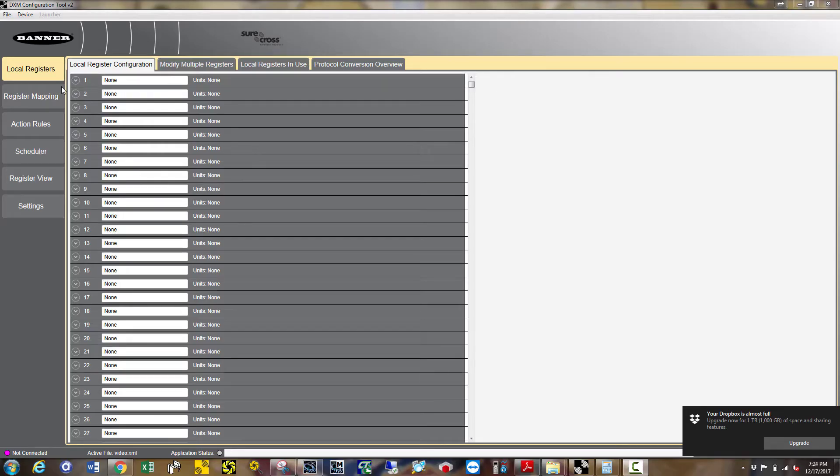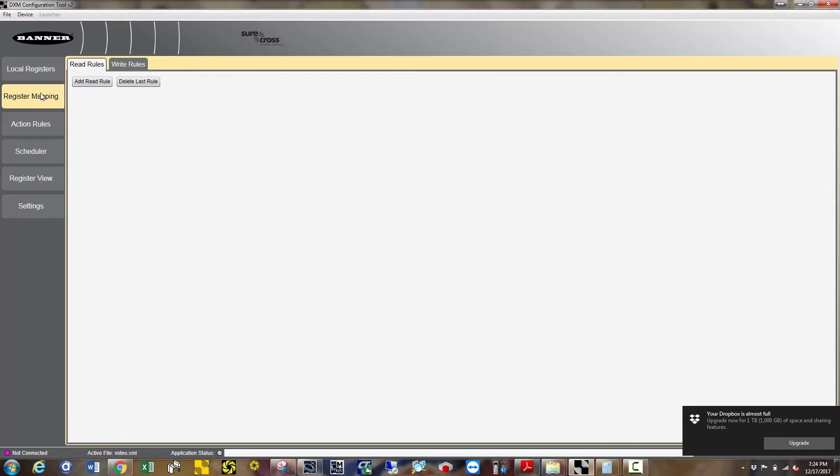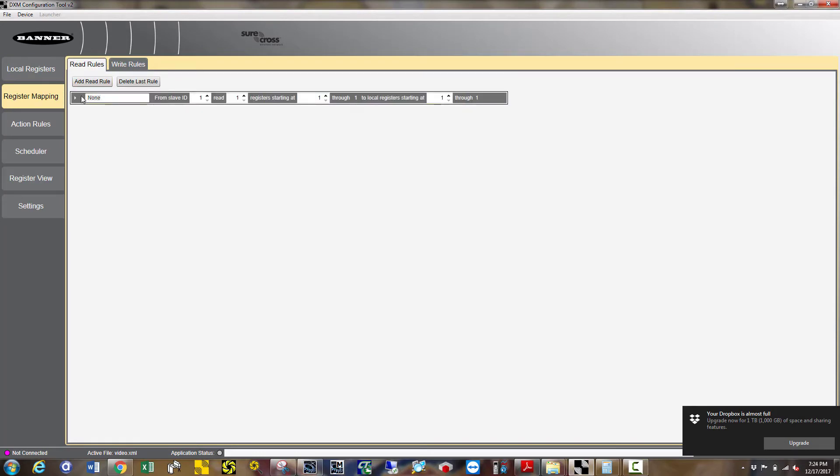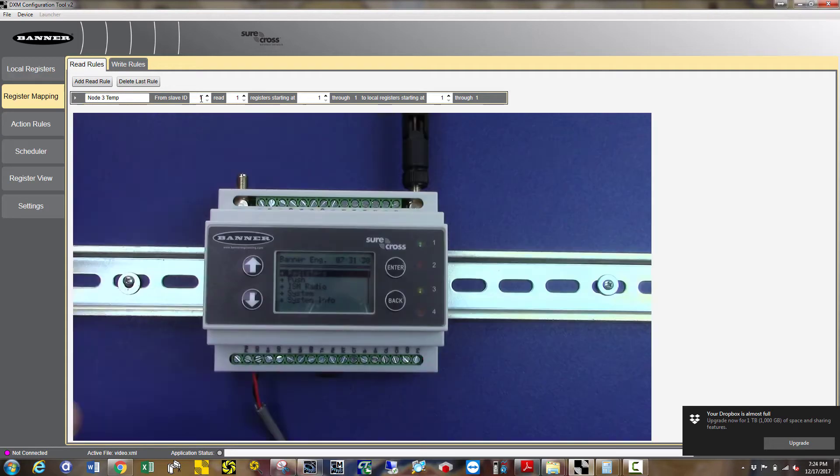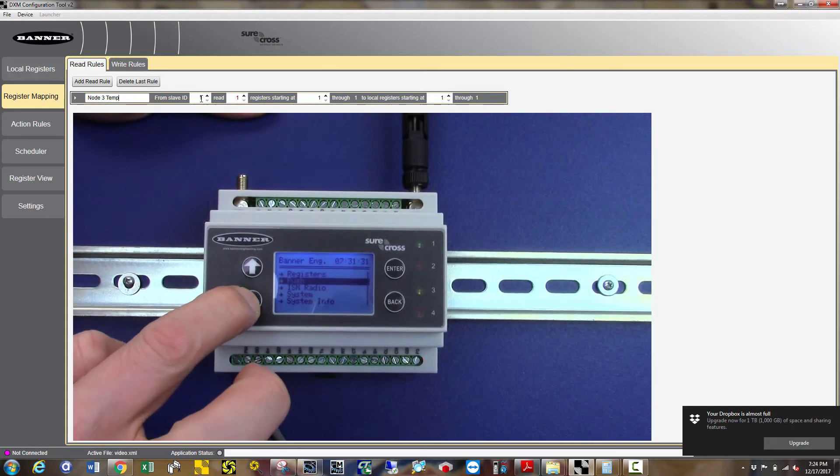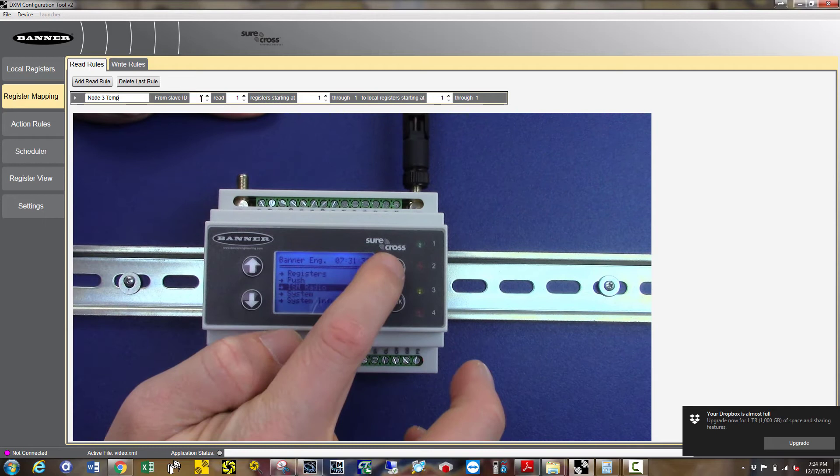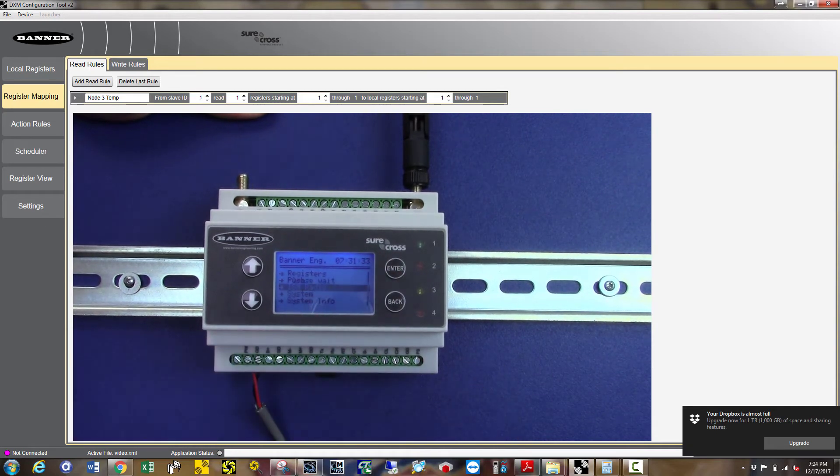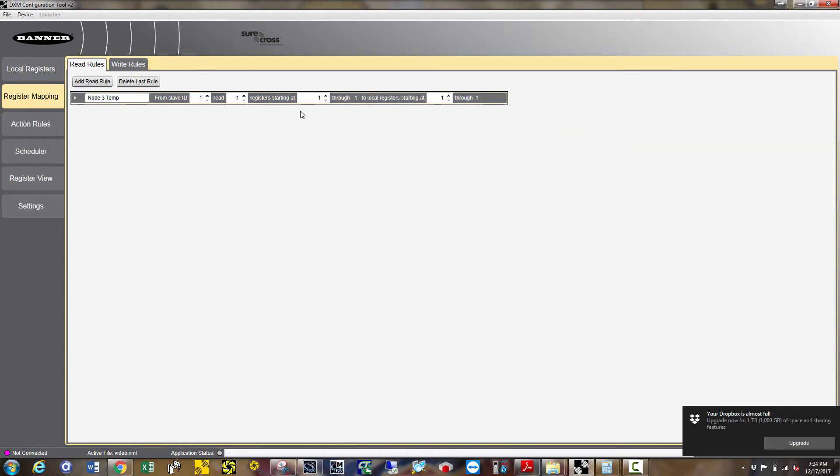Under register mapping, we are going to add a read rule. Enter in Node 3 temp. This is simply a description you use to identify your parameters so you can enter what makes sense to you. From slave ID 1, which is the ID of your DXM, read 1 register 51 to local register 51. You can choose any local register you want, but I recommend to keep your local registers the same as the node registers.